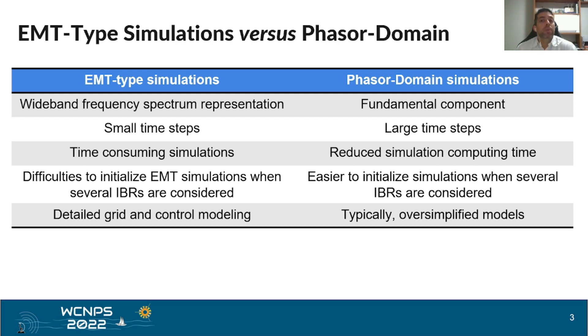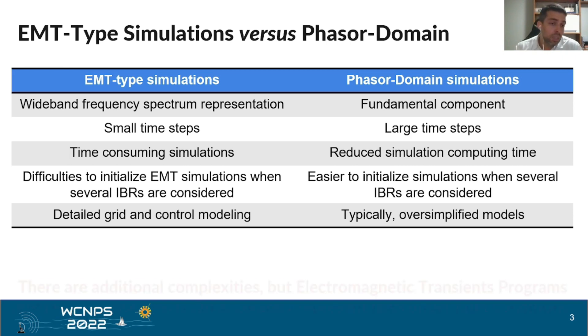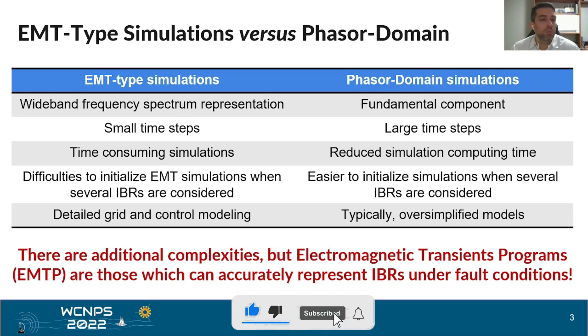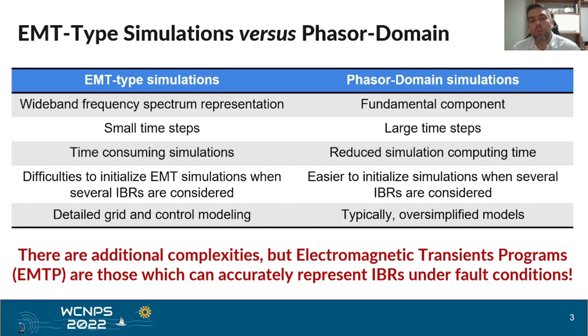On the other hand, when we consider phasor domain simulations, they focus only on the fundamental component, such that large time steps can be used, reducing the simulation computing time. They are also easier to initialize when several IBRs are considered. But typically these simulations consider oversimplified models, which can be unrepresentative depending on the transient events that affect protection. Based on this comparison, we can conclude that there are additional complexities when using electromagnetic transient programs, but these programs are those which can accurately represent IBRs under fault conditions, including all transient events relevant to a protection study with IBRs.